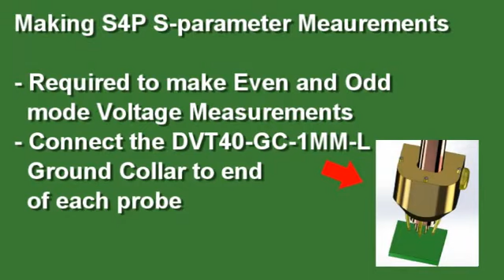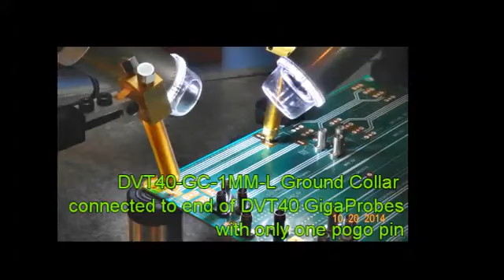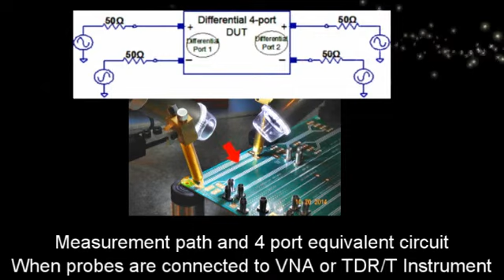To measure S4P S-parameter measurements, attach the ground collar to the end of the DVT probe. Using two DVT40 probes with ground collars provides a ground path for each of its two probe tips to acquire both odd and even waveform measurements. With two probes, we can measure a full 4-port differential S-parameter of this transmission line. Setup complete. In minutes, you are ready to go from storage case to complete multi-mode measurements.